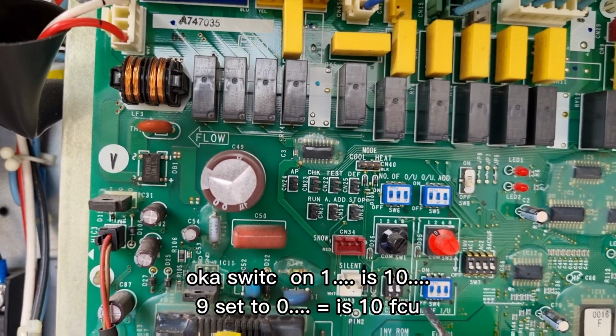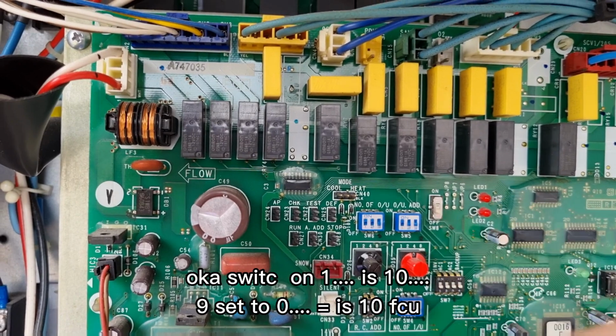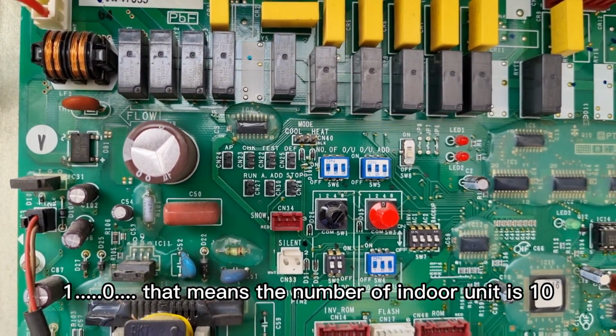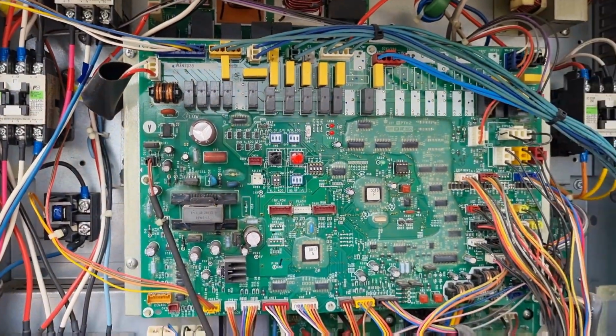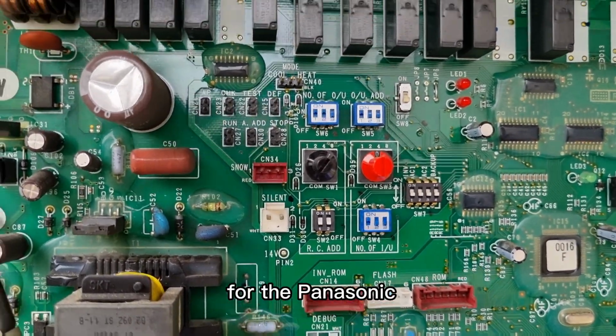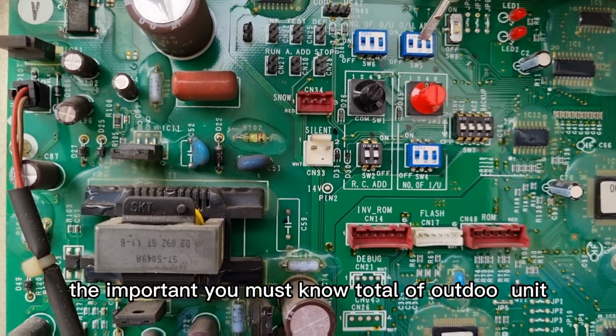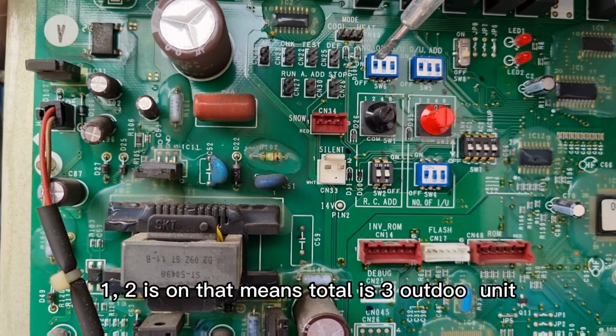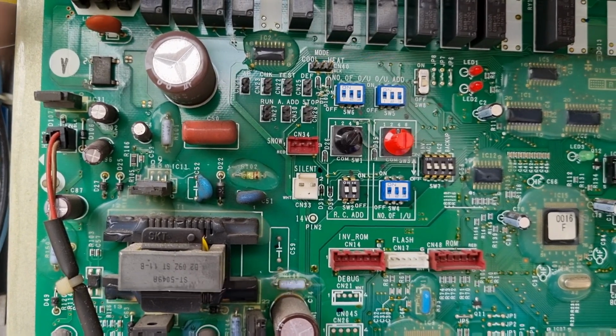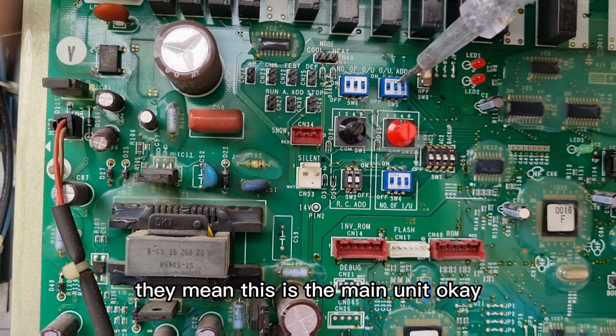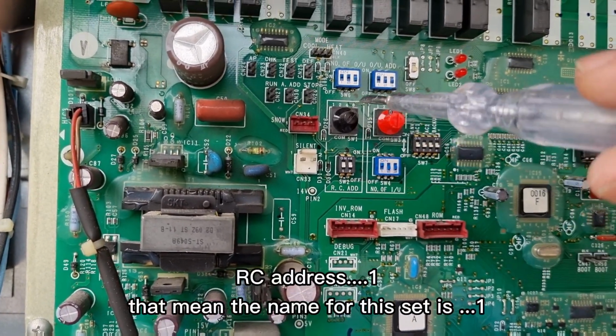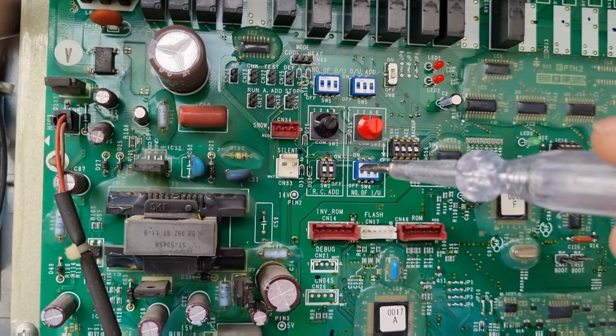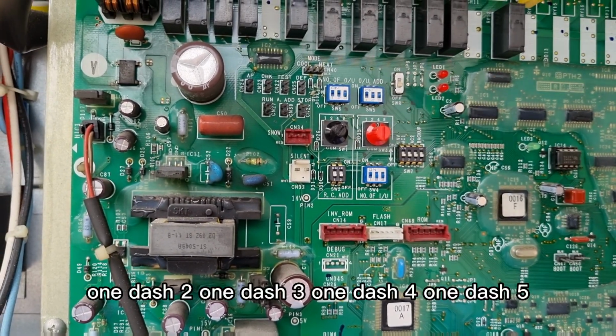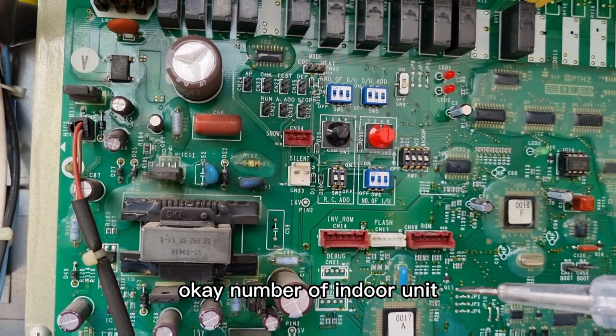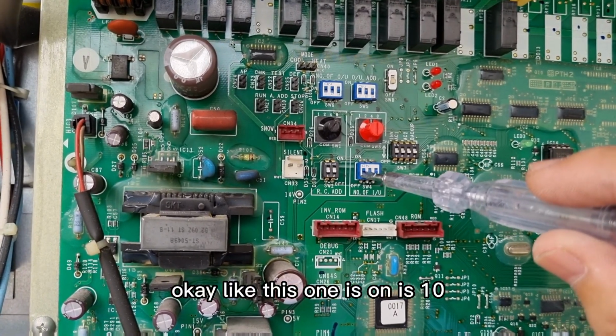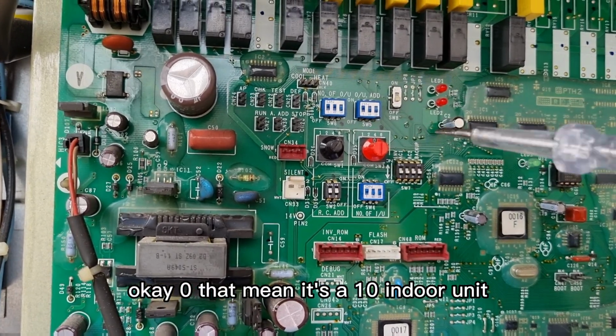Okay, 10, 1 is 10, on. Okay, 9 set to 0 is 1, 0. That means the number of indoor units is 10. Okay, we on back the power supply. For the Panasonic, the important thing you must know is the total number of outdoor units. Okay, 1, 2 is on, that means total is 3 outdoor units. Outdoor unit address 1 means this is the main unit. Okay, RC address means the name for this set is 1. Like the indoor units 1-2, 1-3, 1-4, 1-5, this is the address. Okay, number of indoor units, like this, 1 is on, is 10. Okay, 0, that means it's 10 indoor units.